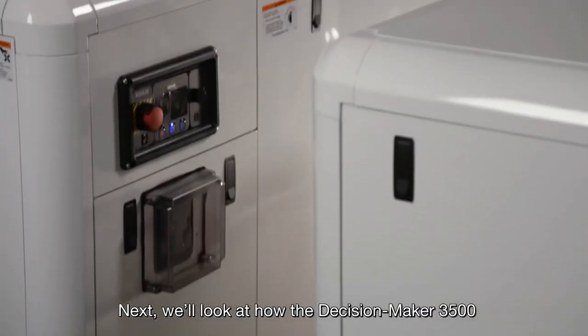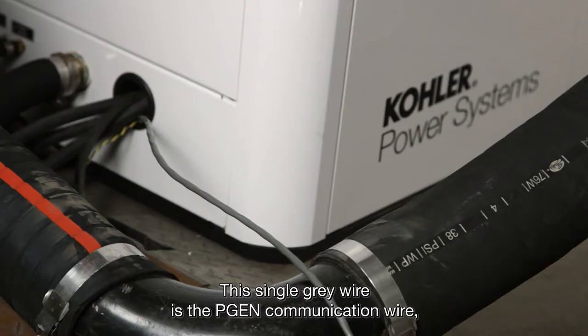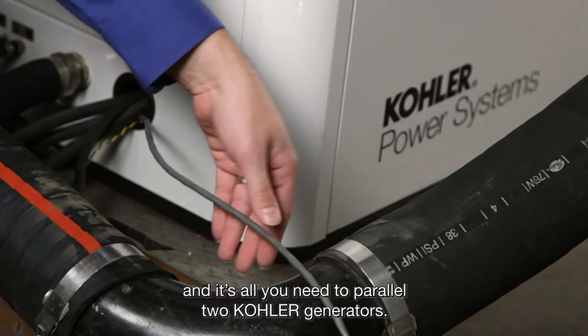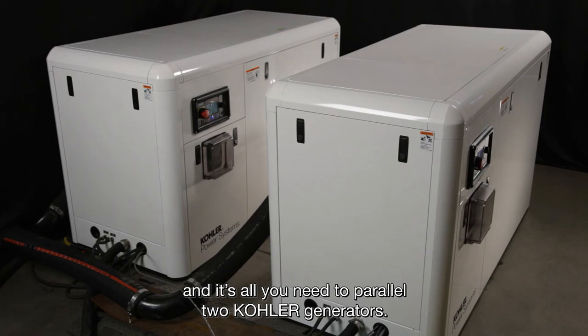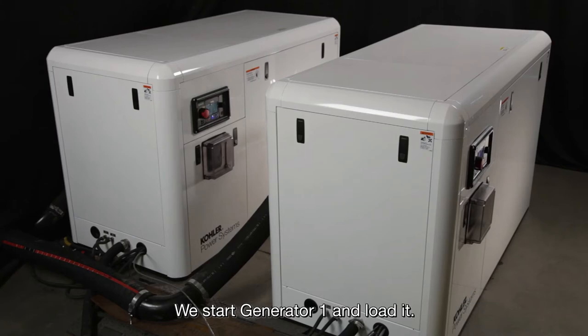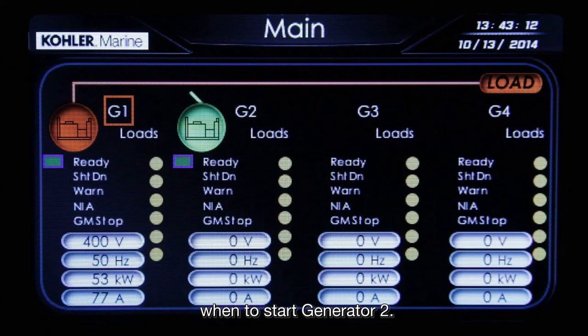Next, we'll look at how the Decision Maker 3500 manages load with two gensets operating in parallel. This single grey wire is the PGEN communication wire and it's all you need to parallel two Kohler generators. We start generator 1 and load it. As the load increases, the system automatically senses when to start generator 2.